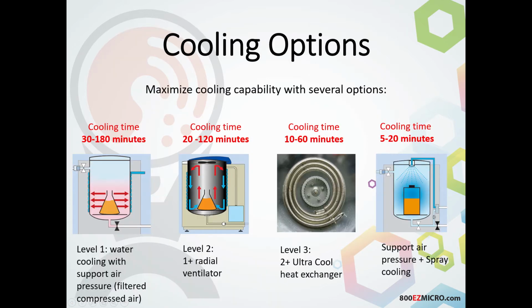Now we'll go through a few of our cooling options. So we have several different levels of cooling options to maximize the cooling capability of the system. Level 1 is what we call just our cooling with compressed air. So the cooling with support air pressure, what we would do at that point is, at the end of sterilization, inject sterile compressed air into the unit to push the steam out of the system. So that way we've removed the heating agent, but we've maintained the pressure the way that it should be, so the liquids won't boil over. So as we've done that, then we run the cooling coils. The cooling coils will radiate to the vessel, cool it down to 80 degrees, then we will release the air pressure that we put in and allow the user to access the system.